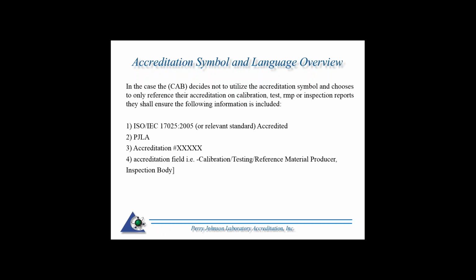What needs to be referenced is the standard, in this case ISO 17025:2005, or the relevant standard. The AB, which is us, PJLA, your accreditation number, which is unique to your organization, and then the accreditation field: your testing, calibration, reference material producer, or inspection body.